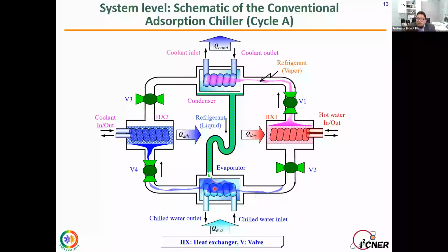In the adsorption cooling system, we need 4 heat exchangers. The bottom part is our evaporator, and the top part is our condenser. And we have 1 pair of heat exchangers, which are identical in principle. In our system, initially we used a silica gel water-based system. We pack silica gel inside the fins, and we have used a net to pack it so that the silica gel never drops out. And here you have our copper tube, so that the heat transfer fluid can go through these tubes.